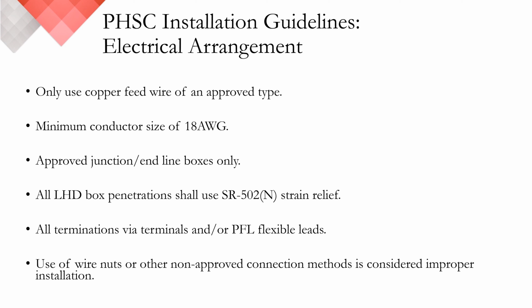They also come equipped with the appropriate terminal blocks to accommodate the detector being used. Again, CTI requires the Type T terminal block because of our thermocouple principle. So we've developed a specific part number to make sure that you're getting the appropriate equipment. And of course, the use of wire nuts or any other non-approved connection method would be considered improper installation techniques and could possibly void warranty.